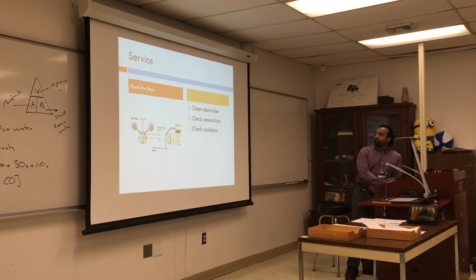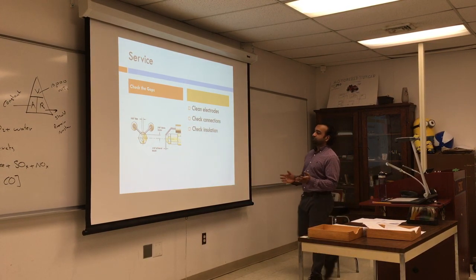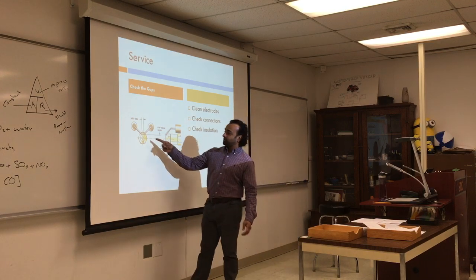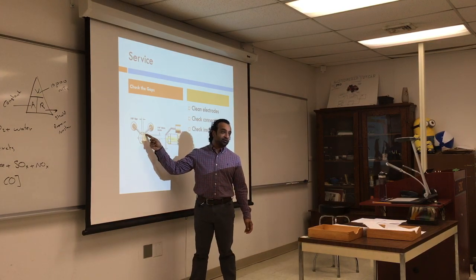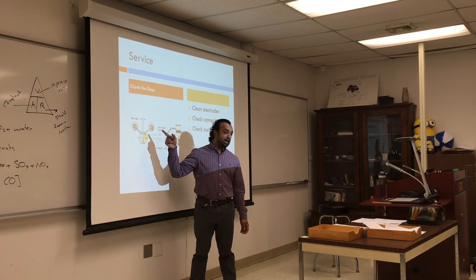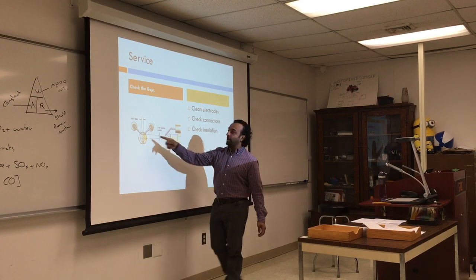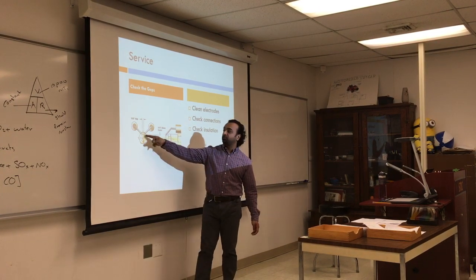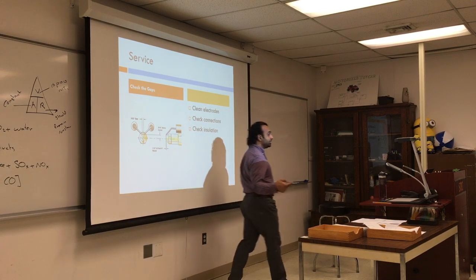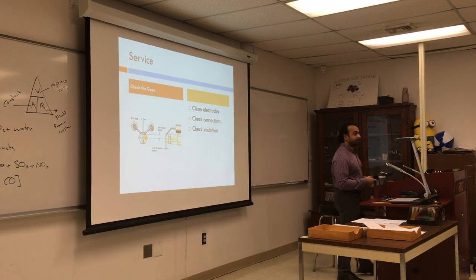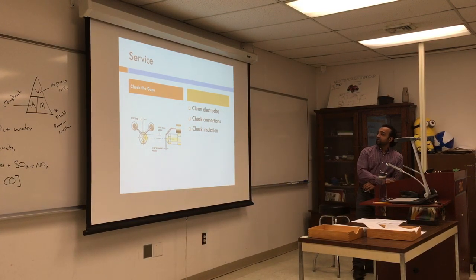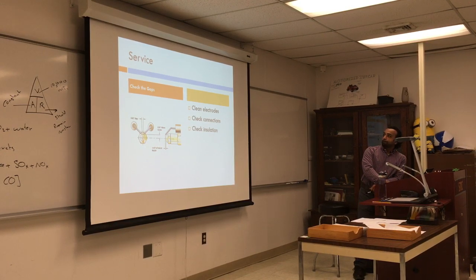Gaps are very important. So clean the electrodes. If those tips are designed to be pointy and they're all worn out, you have to change those. The gap makes a difference, and this tip makes a difference, and will give you clean conductivity, and the spark will jump clean between those two electrodes. Check connections, and also check insulation.